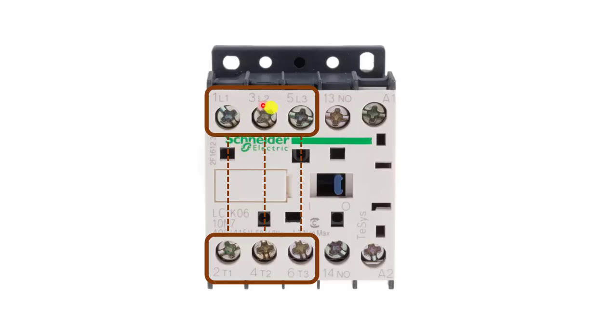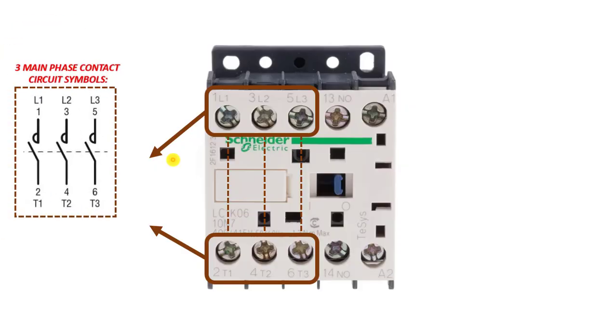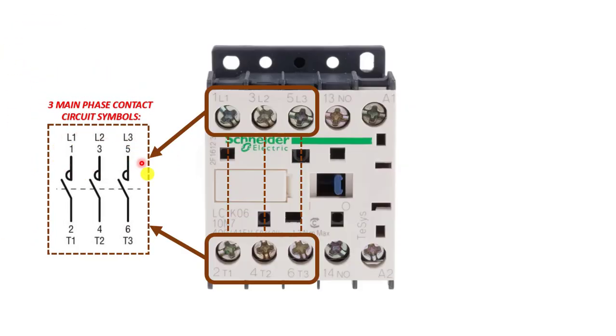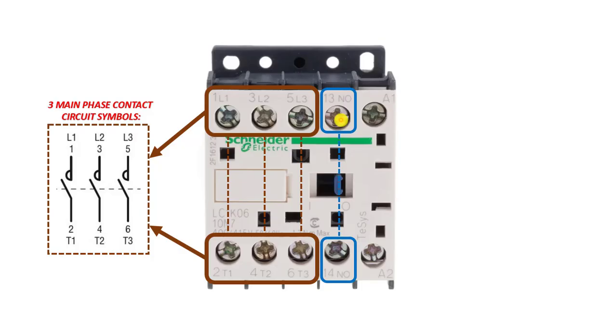The electrical circuit symbol shows three open main contacts. The input phases are L1, L2, L3 and the output phases from the contactor are T1, T2, T3. We also have an auxiliary contact. This auxiliary contact is marked NO, meaning normally open — this is our open auxiliary contact.